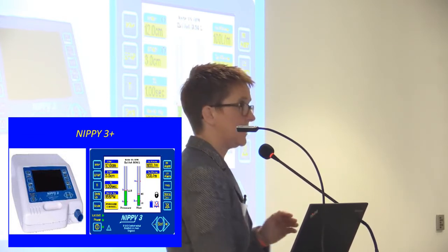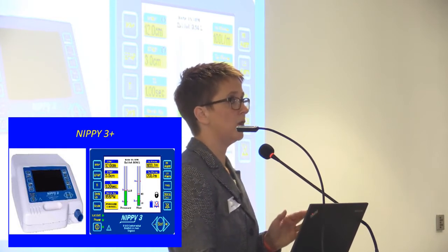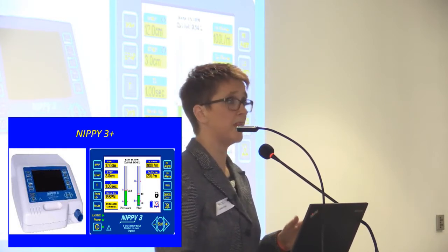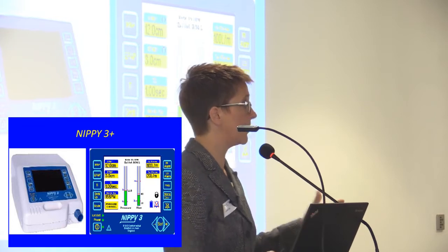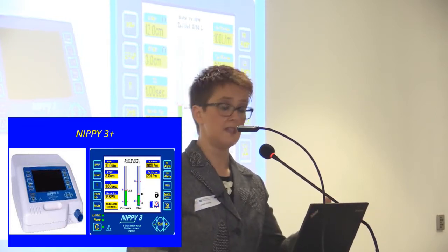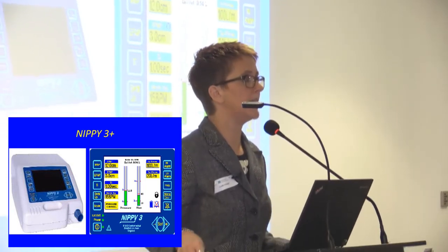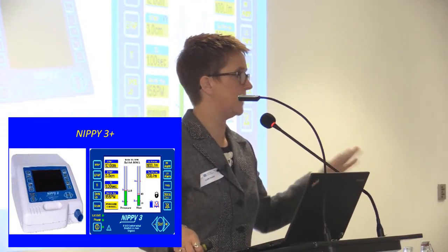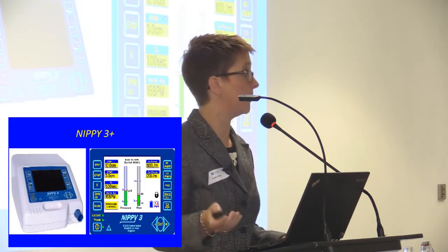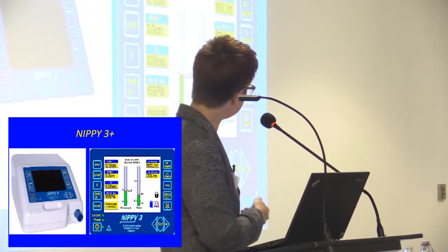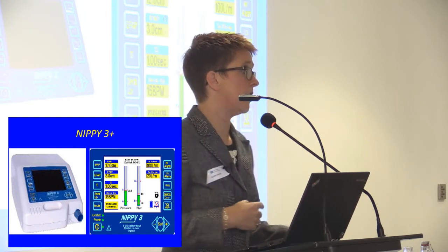The 2 things that we teach carers and the patient are the high flow and low flow alarms, because obviously this is a breathing apparatus, so we have to make sure it alarms if things like disconnection happen, if the patient takes a mask off in the middle of the night, or if there should be a high flow leak, something just come apart from the machine, that it will activate. And the low flow alarm is the opposite.